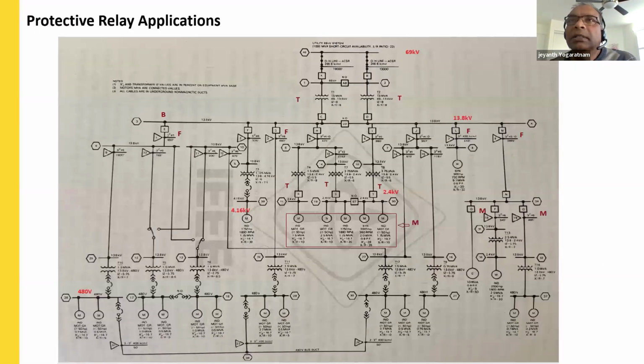So this is another single line diagram from another plant, and technically I took this one in order to explain what type of protections are being applied depending on the devices connected to the bus. So the main supply is coming from 69 kV, that steps down to 13.8 kV level. And further, we will be able to see you have a 2.4 kV bus as well as 4.16 kV level.